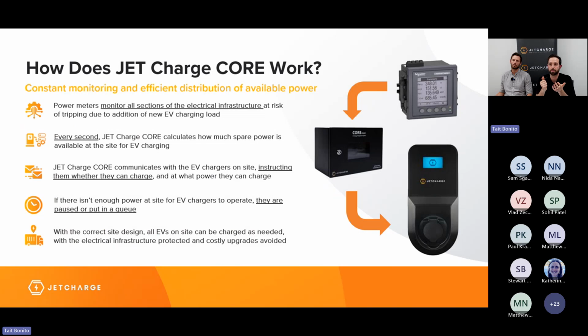And so if all of a sudden there were an increase in non-EV charging power draw at the building, say everyone's put on their aircon, significantly increasing the power draw at the building, Core will be able to monitor and calculate how much new spare capacity there is after that instance, and will instruct the EV chargers to reduce their power if it's determined that there isn't sufficient spare electrical capacity for all the EV chargers to operate at their maximum output. And if there isn't enough power available for all the EV chargers to operate, their charging will be paused, and some of them would be put in a queue. And then every hour, the Core Load Management System rotates the chargers in the queue to make sure those EVs charging all get an equal and fair amount of charge.